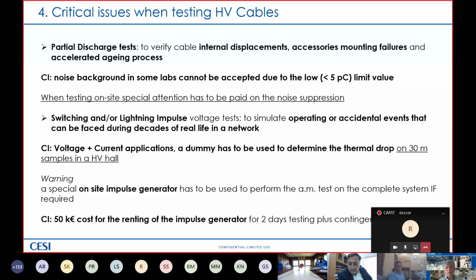This can happen during production, accessory mounting failures, and accelerating aging process. The critical issue is that if you perform this measurement during a type test, you can do it in a lab. But if you do it during a qualification test, the noise background is very critical. So in a lab, we cannot accept a background noise level greater than 5 picocoulomb. And during on-site testing, special attention has to be paid to noise suppression.